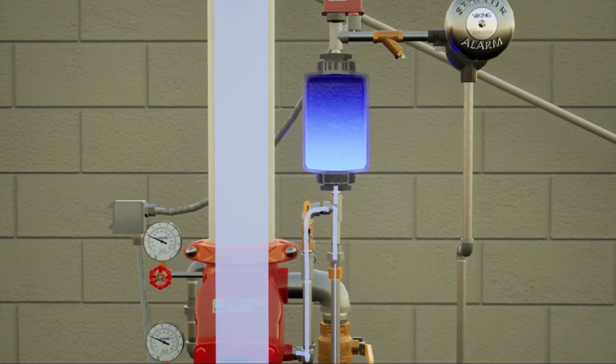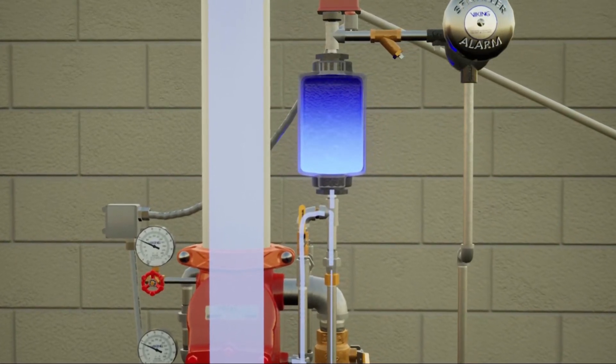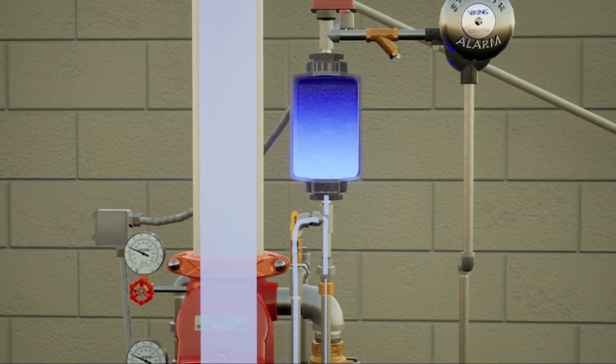The alarm line is equipped with a 1/8-inch restricted orifice that allows the retard chamber to externally drain and reduces false alarms.